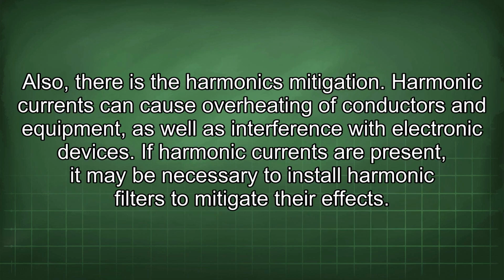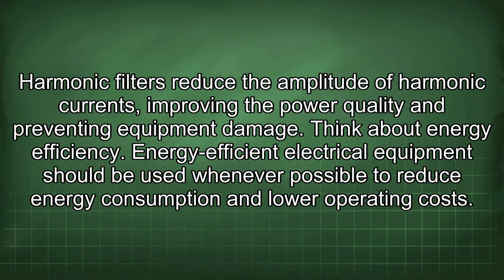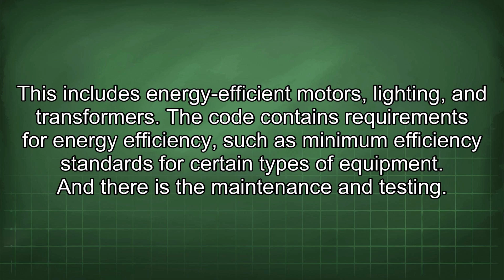Also, there is the harmonics mitigation. Harmonic currents can cause overheating of conductors and equipment, as well as interference with electronic devices. If harmonic currents are present, it may be necessary to install harmonic filters to mitigate their effects. Harmonic filters reduce the amplitude of harmonic currents, improving the power quality and preventing equipment damage. Think about energy efficiency. Energy-efficient electrical equipment should be used whenever possible to reduce energy consumption and lower operating costs. This includes energy-efficient motors, lighting, and transformers. The code contains requirements for energy efficiency, such as minimum efficiency standards for certain types of equipment.